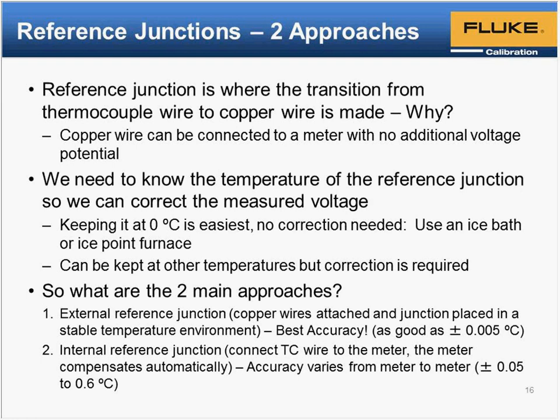You can then test the wire and make sure that it complies with the allowed range of voltages that are applicable for that thermocouple. If you keep the reference at another temperature, like room temperature, you have to compensate for that. You have to know what the temperature is and then convert that to an offset and cancel that from your reading.